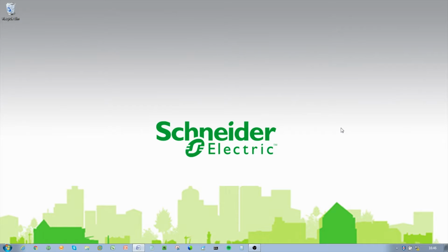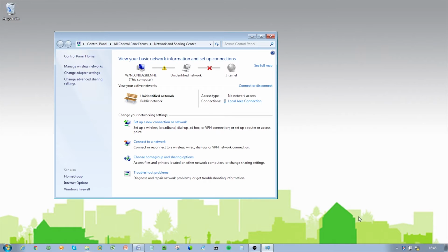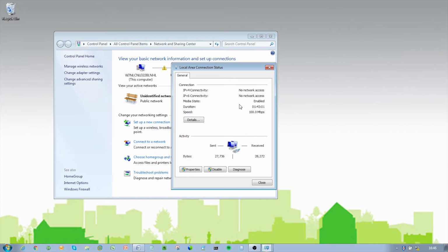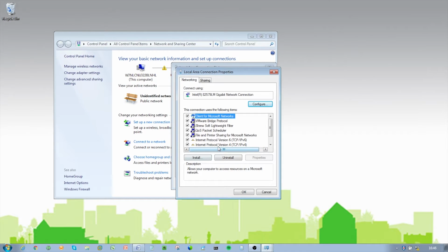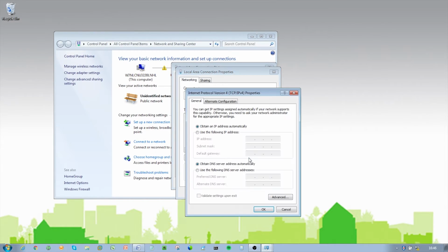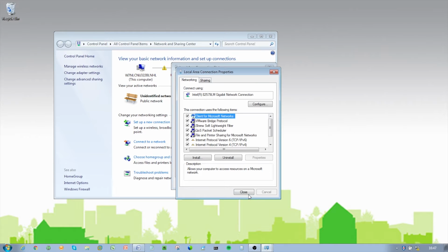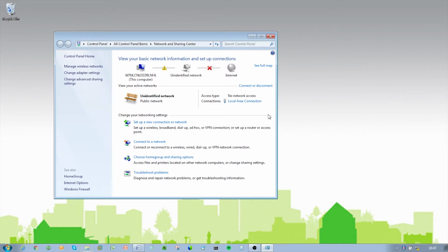Establishing communication with the TrioQ data radio. Ensure the TrioQ data radio has been factory cleared. The factory default IP address of the Q data radios is 192.168.2.15. You will need to set the IP of your PC in the same range, for example 192.168.2.10, and default subnet mask. Connect your PC Ethernet port to one of the Ethernet ports.